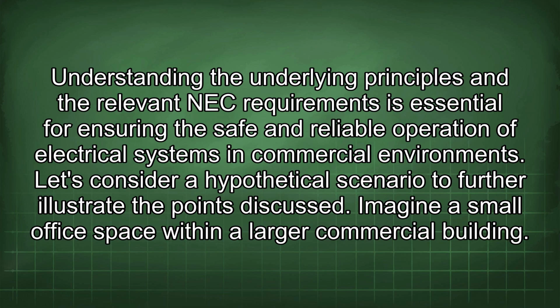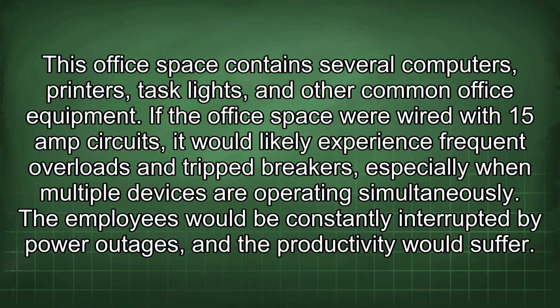Imagine a small office space within a larger commercial building. This office space contains several computers, printers, task lights, and other common office equipment. If the office space were wired with 15 amp circuits, it would likely experience frequent overloads and trip breakers, especially when multiple devices are operating simultaneously. The employees would be constantly interrupted by power outages, and the productivity would suffer.